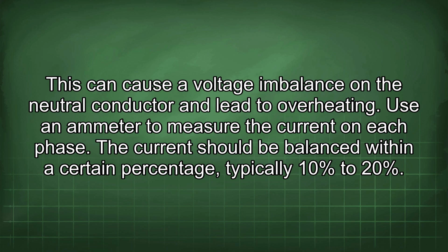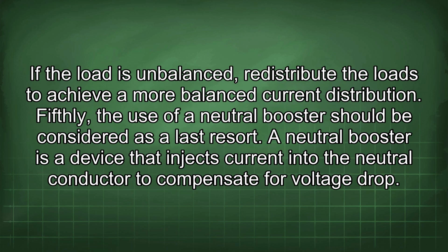Use an ammeter to measure the current on each phase. The current should be balanced within a certain percentage, typically 10% to 20%. If the load is unbalanced, redistribute the loads to achieve a more balanced current distribution.